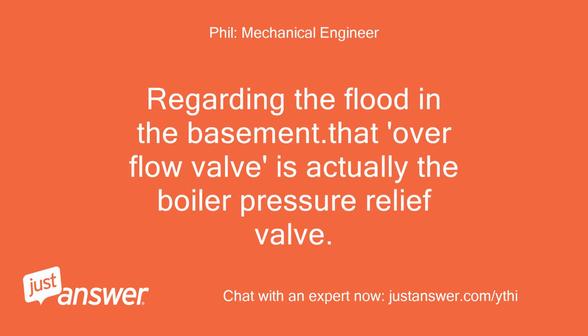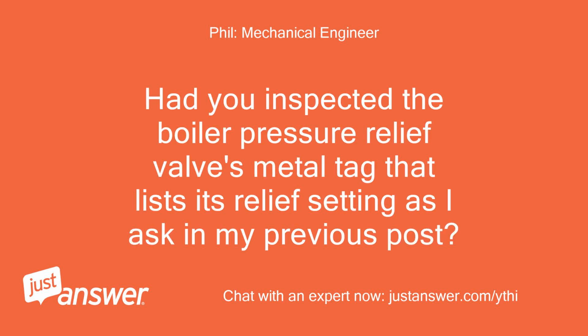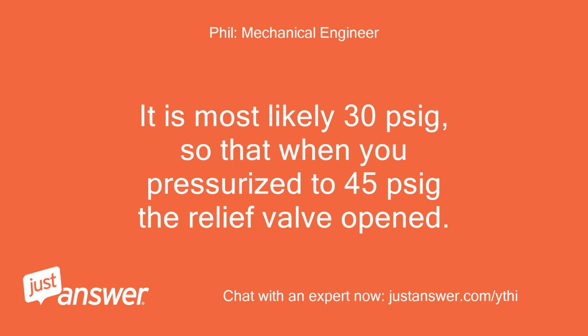Regarding the flood in the basement, that overflow valve is actually the boiler pressure relief valve. Had you inspected the boiler pressure relief valve's metal tag that lists its relief setting as I asked in my previous post? It is most likely 30 psig, so that when you pressurize to 45 psig the relief valve opened.